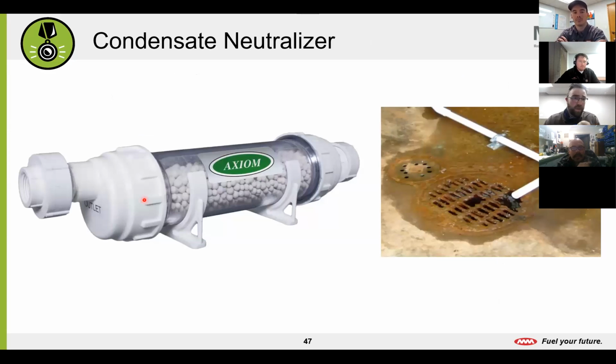See here, we'll skip ahead for a second. The way we have to address that water here is we got to put it somewhere, right? So whether we're pumping it out through a condensate pump or we're draining it to a gravity drain to a floor drain or what have you, out the side of the building if our boiler is high enough that we can drain it through a wall. But being flue gas, right? It's combustion byproduct. That's not drinking water by any means. That water is very acidic.